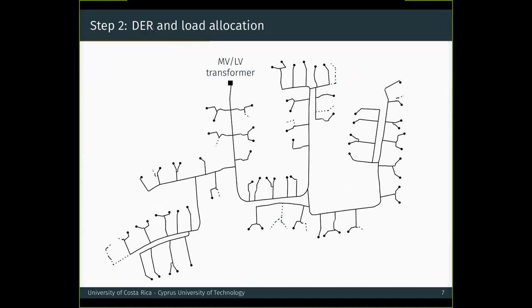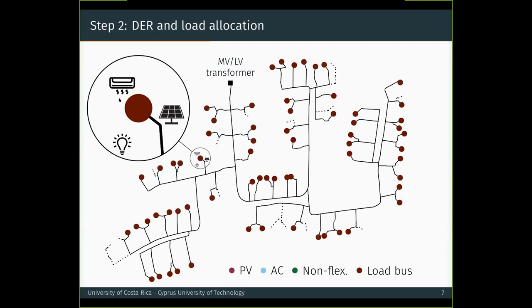After that, in the second step, we allocate DERs and loads. Our approach is simple. We simply define a penetration level and allocate, say, PV units in 20% of the load buses. Allocating here means that we know which reactive and active powers would be representative for a PV unit and we assign it to each of these buses. To name more examples, we could allocate air conditioning units similarly, and we could allocate non-flexible loads in a much larger percentage of load buses. In the end, we would add up the corresponding powers, and if we zoom in on a given load bus, we would see a realistic load consumption.